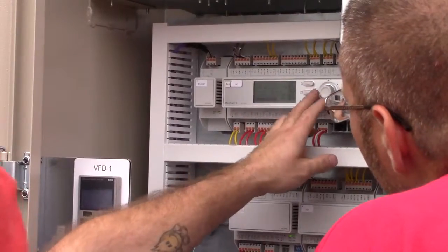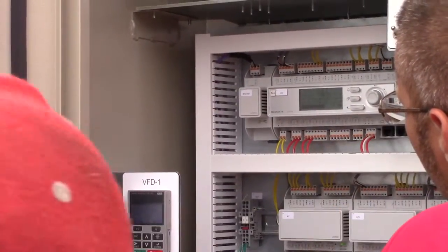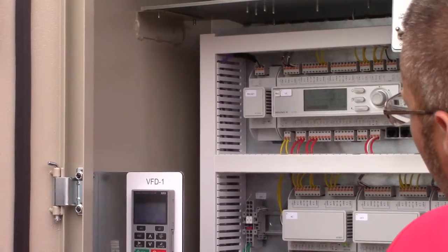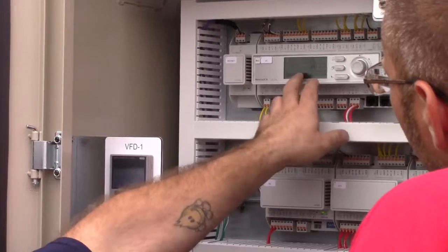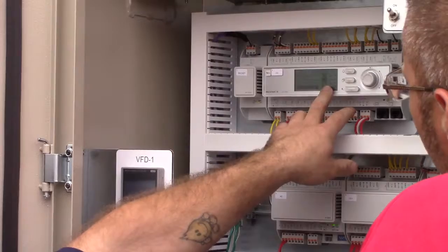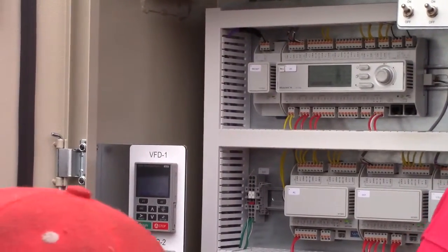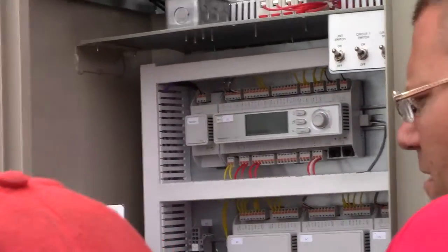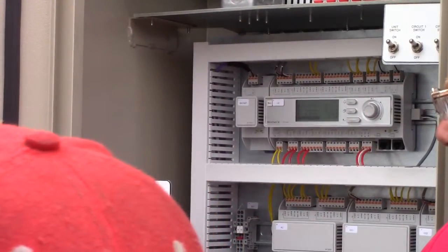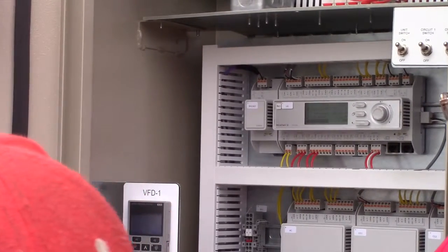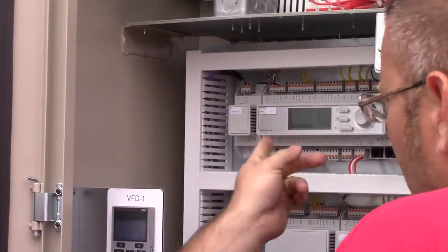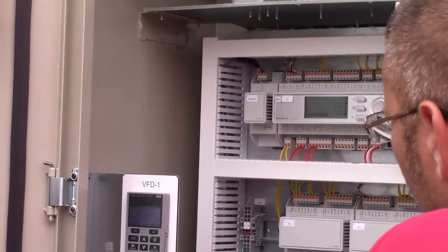And then the other thing is oil pressure. So we read oil pressure as the difference between condensing or discharge pressure and an oil pressure sensor. It's across our oil filter. So if you get oil pressure alarms, usually the trip point's somewhere like 36 pounds or so. If this starts going past 25 or so at full load, you might want to start thinking that your oil filter might need to be changed. We don't say do it based on hours of operation or any of that kind of stuff. We do suggest doing an oil sample once a year at least, but we don't suggest changing that filter until that's a problem. So we monitor that on a pressure basis.